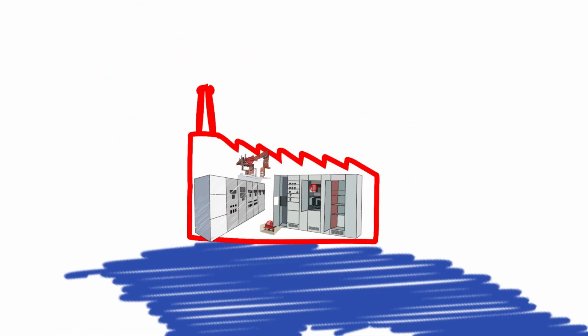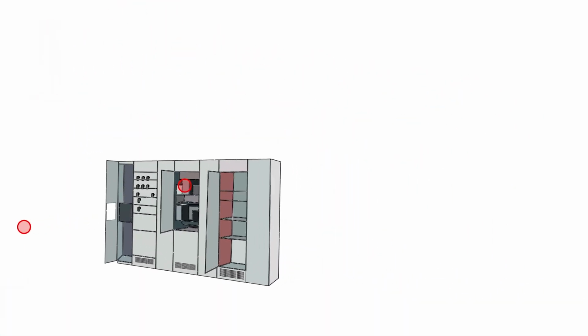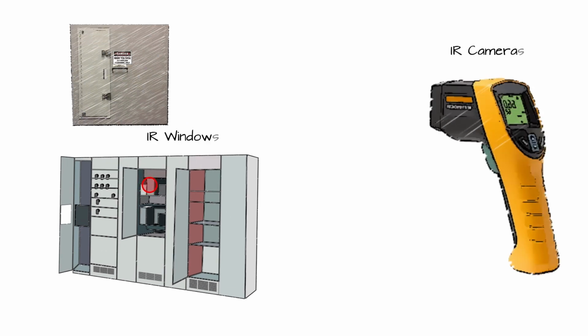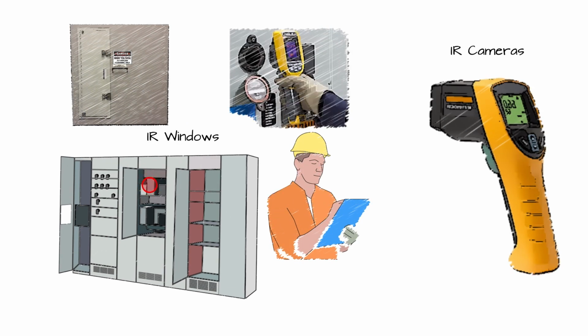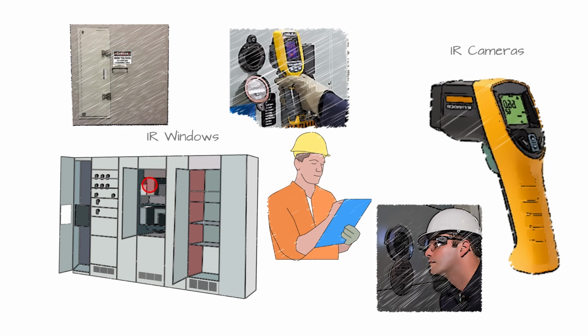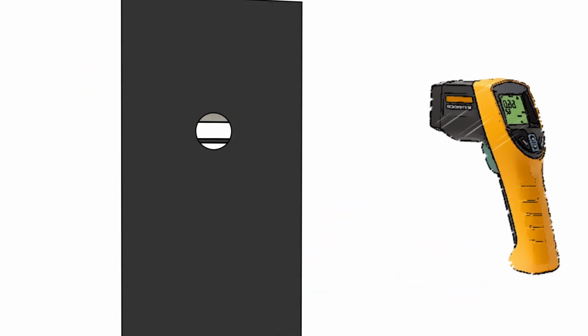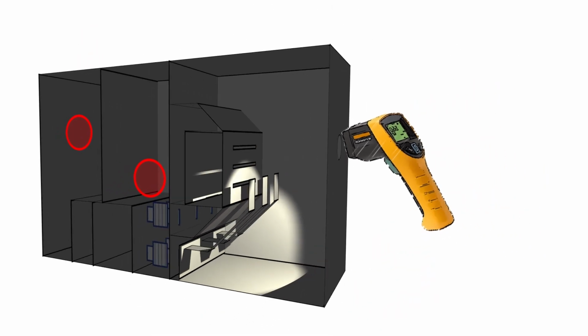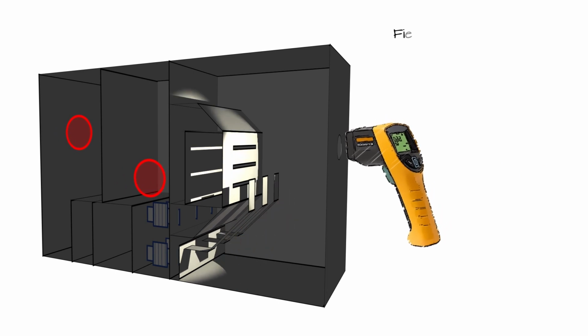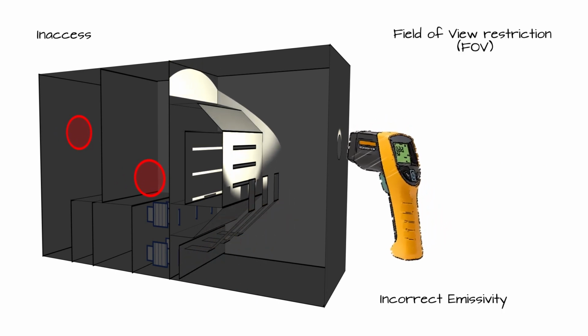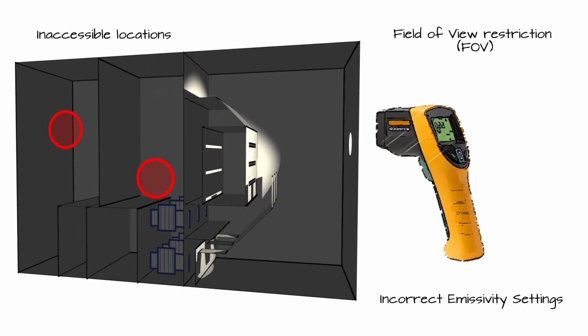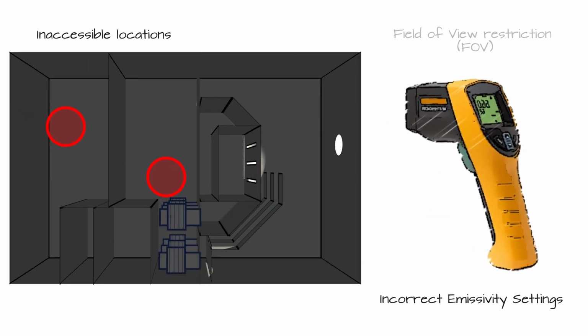To overcome these shortfalls and to measure the temperature of the live conductors, some facilities use infrared cameras and windows. With this method, an IR camera is directed at a live conductor either directly or through an IR window to measure the rise in temperature. In some cases, the IR camera or the window visibility is restricted by the connection location and field of view of the IR window.